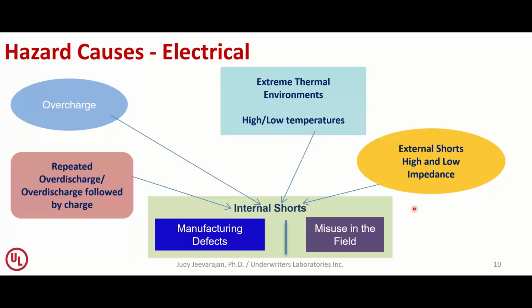Apart from overcharge, we also see a problem with repeated over-discharges. People think that when you over-discharge a battery, it just dies, but that's not always true. You could have subtle over-discharges that can lead to other issues, forming internal shorts and causing thermal runaway at some point, even without you noticing it.